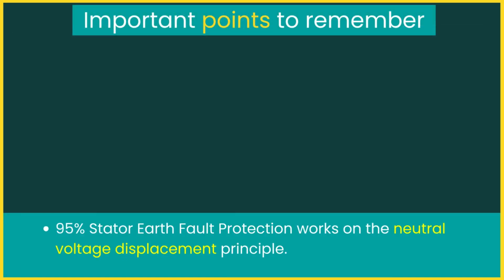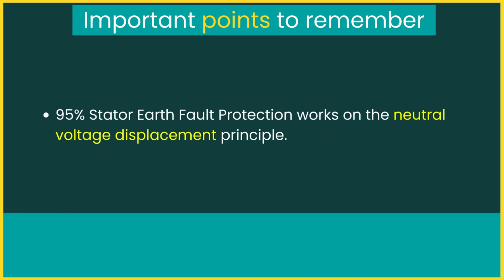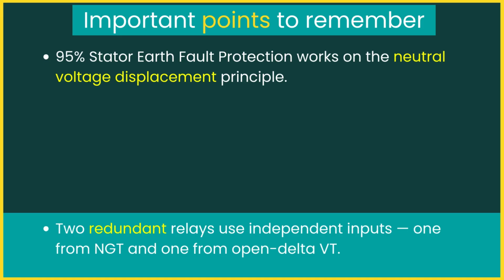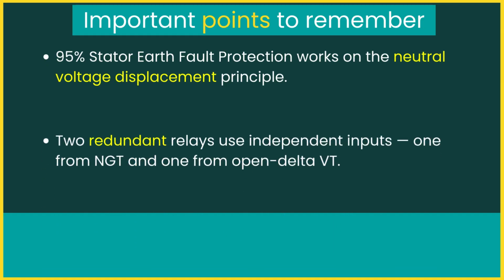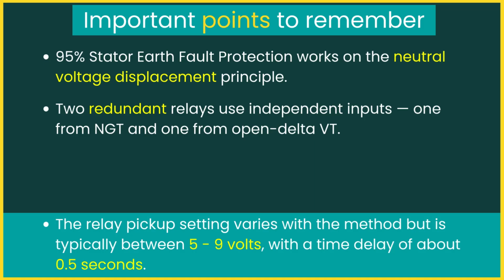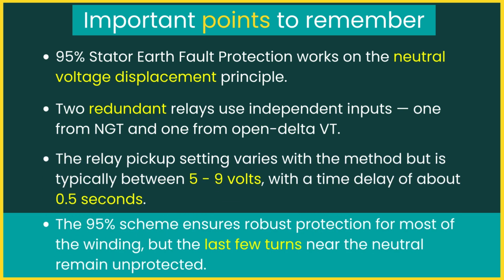Let's recap what we learned in this video. 95% Stator Earth Fault Protection works on the neutral voltage displacement principle. In practice, 2 redundant relays use independent inputs, one from NGT and one from open delta VT. The relay pickup setting varies with the method but is typically between 5 and 9 volts, with a time delay of about 0.5 seconds. The 95% scheme ensures robust protection for most of the winding, but the last few turns near the neutral remain unprotected. That's where 100% Stator Earth Fault Protection comes in, using either the Third Harmonic Voltage or the Subharmonic Injection method. To understand how those advanced schemes complement the 95% protection, check out the 2 videos in this series. Together, they complete the story of comprehensive generator Stator Earth Fault Protection.